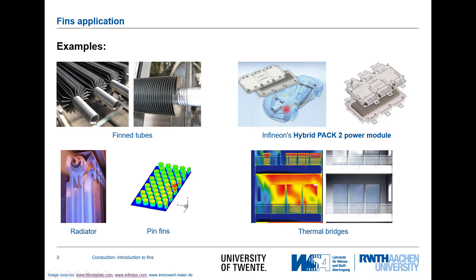Otherwise, the designer would have also applied fins on the inner side. So usually there will be a very good heat transfer on the inside, maybe due to a phase change process such as evaporation or condensation. On the outside, you will probably have a gas which has a poor thermal conductivity, and as such a high surface area is needed for the heat transfer.